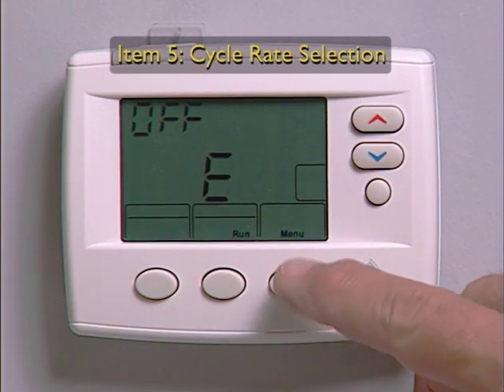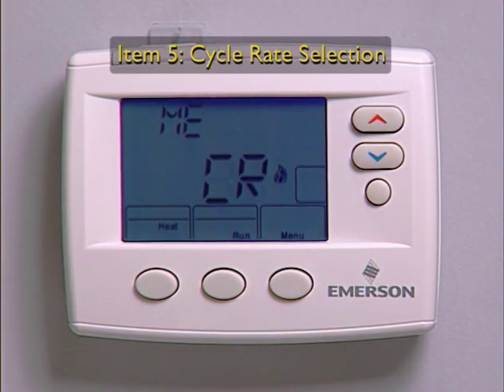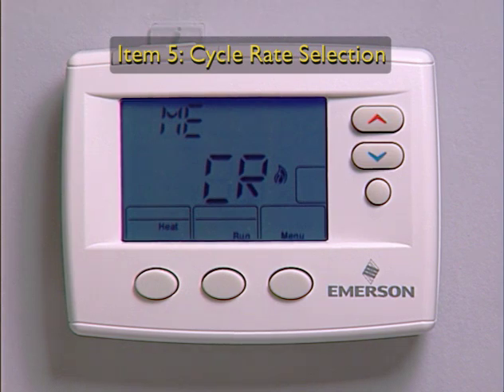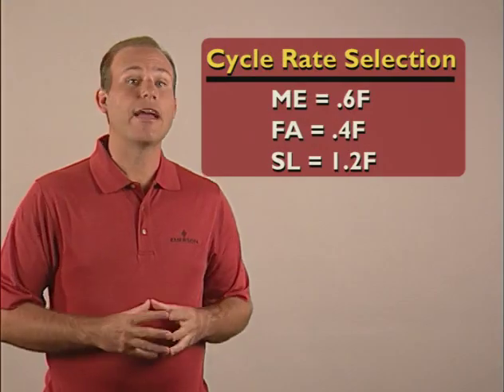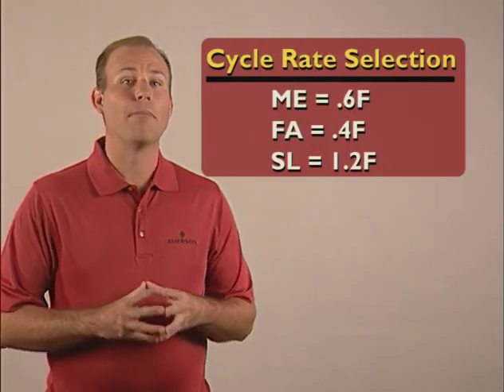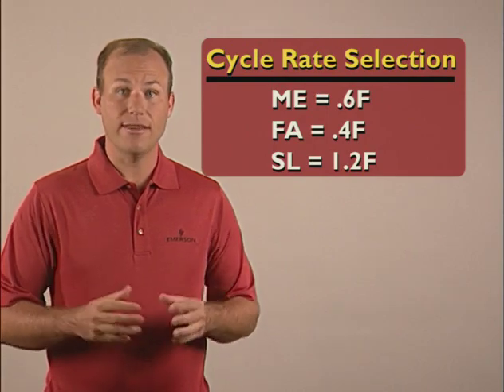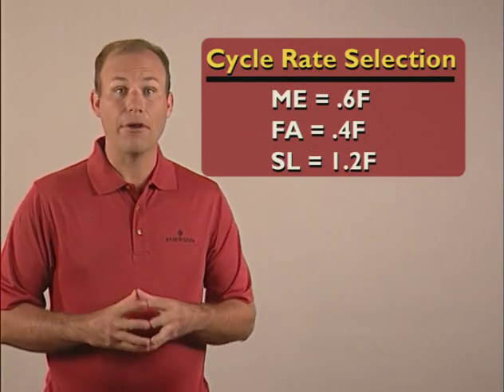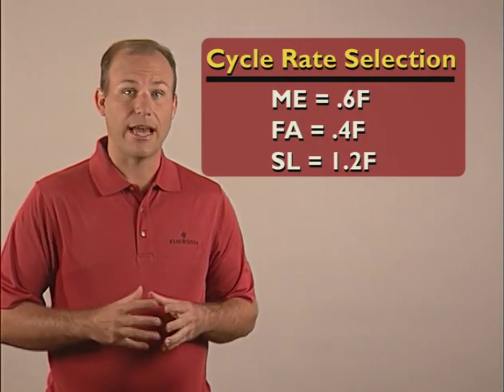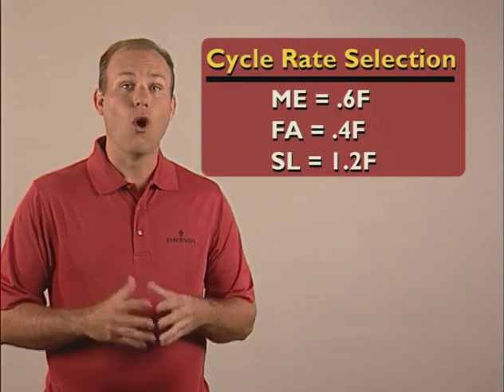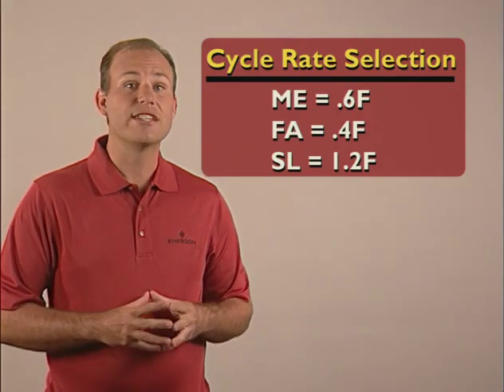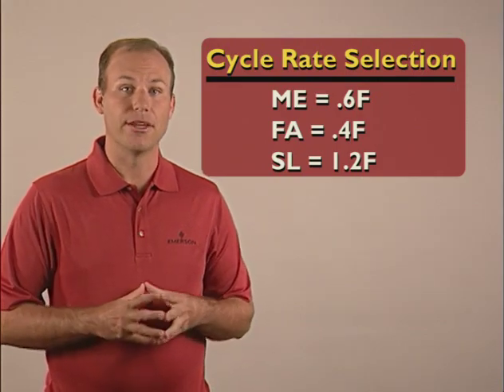Menu option 5 is the cycle rate selection option for the heat function with the default display of MECR and the flame icon. This setting cycles the heat at a medium rate of about 0.6 degrees Fahrenheit. To change it, press the up or down arrows to select fast, which cycles heat at 0.4 degrees, or slow, which cycles it at 1.2 degrees.